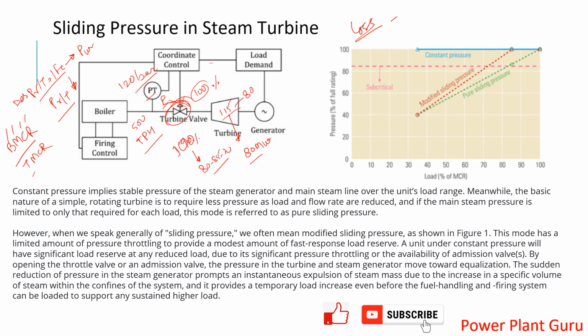What is sliding? Based on 100 megawatt, there will be a set point based on turbine loading. The boiler pressure will change. Let's say it reduces for 80 megawatt, then it is a different pressure. Let's say it reduces to 75 megawatt, then it is again a different pressure. So based on the load, or the steam demand by the turbine, the pressure is changing.